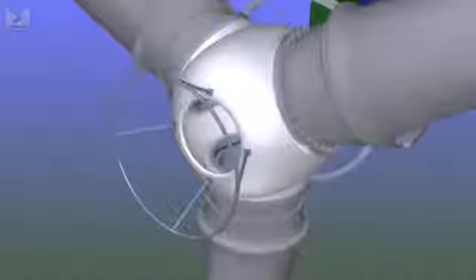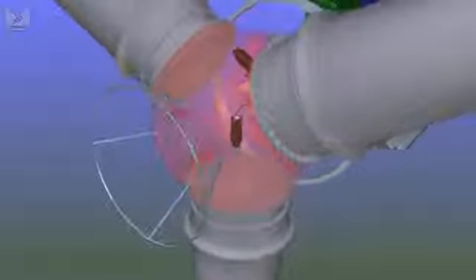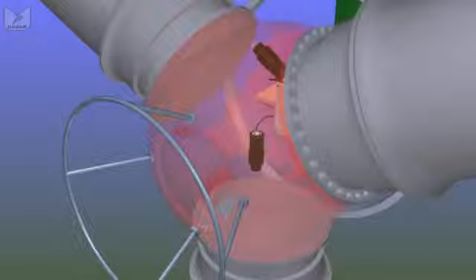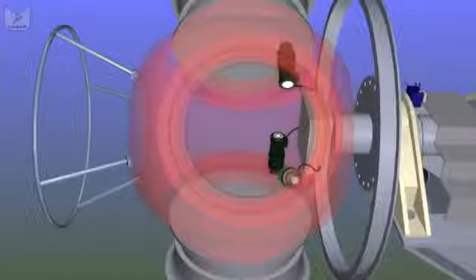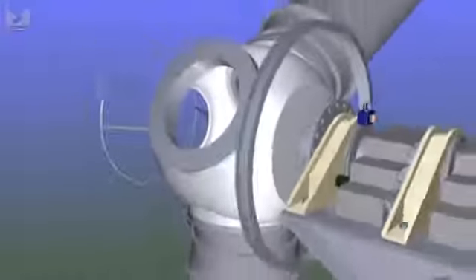And you access the hub through the gap between this fibreglass cowl and the cast hub. It's a bit of a wriggle, but you wriggle through, usually feet first. Crawl through the hole in the middle of the hub. And inside the hub, we'll find the control electronics, the pumps, the motors and the batteries to control the pitch of each blade, rotating it on its own bearing to set the optimum angle for the wind. If we turn the blades through 90 degrees, so they're edge onto the wind, there's no net turning force. It's a process called feathering, and the turbine will stop.